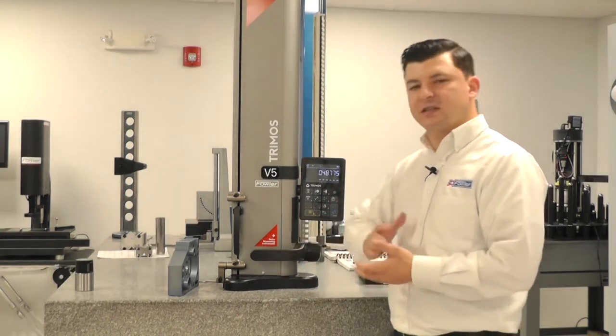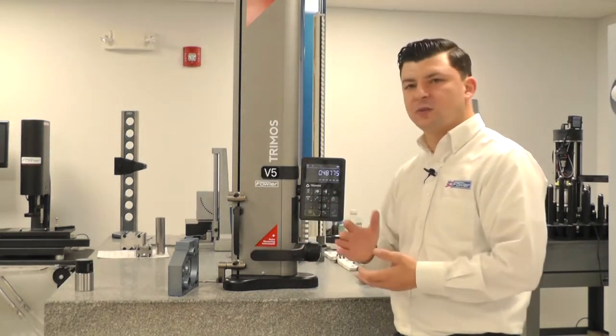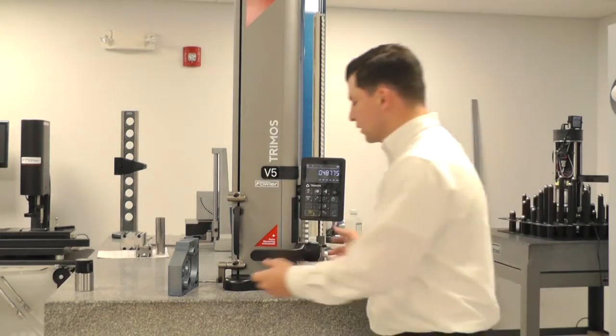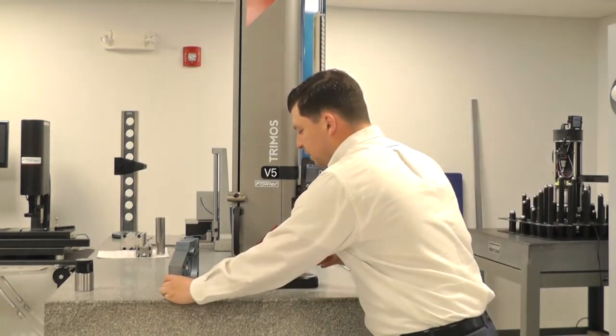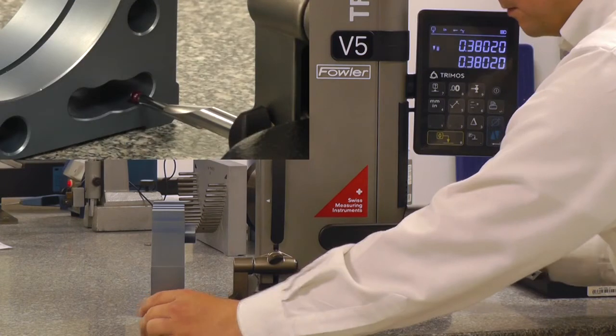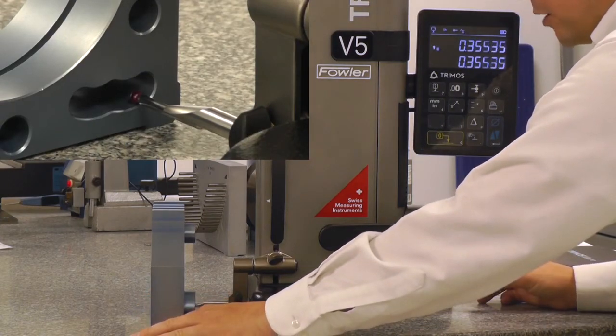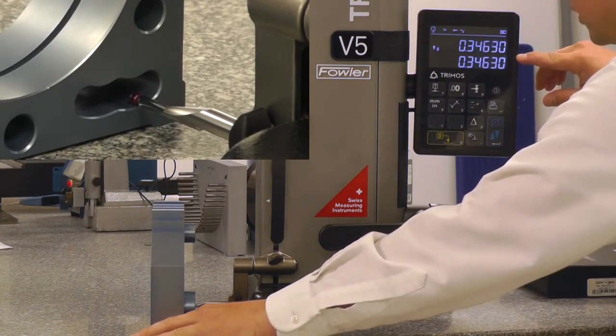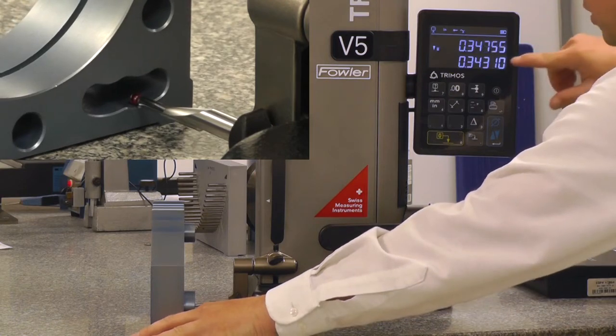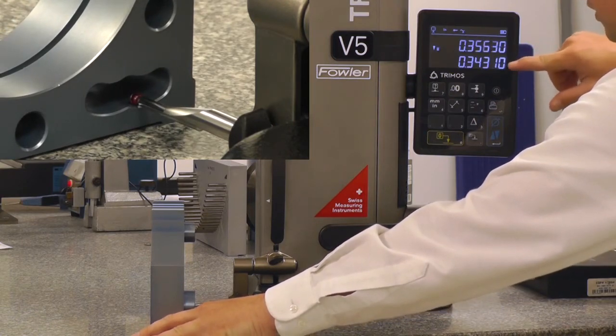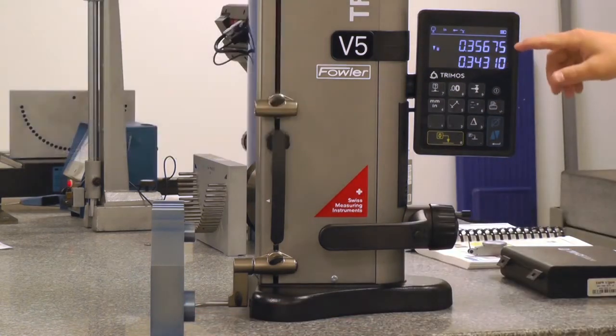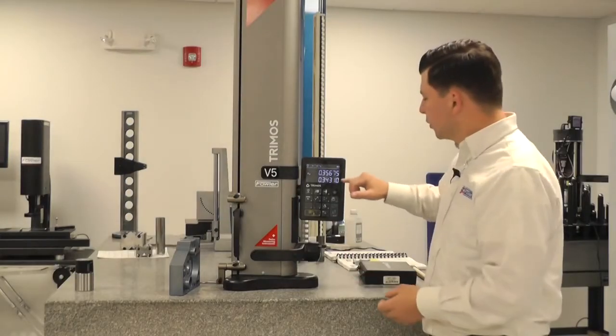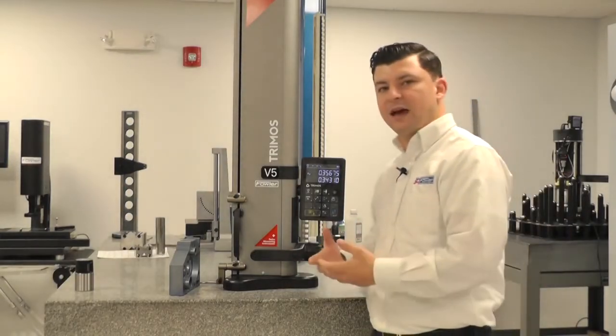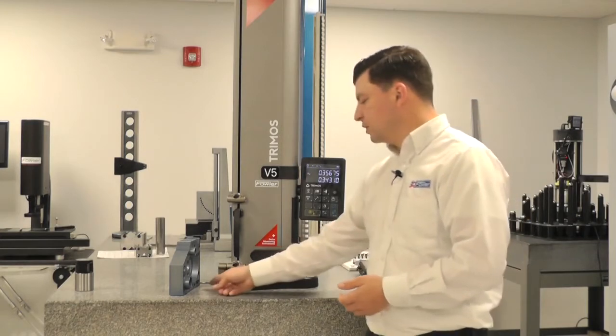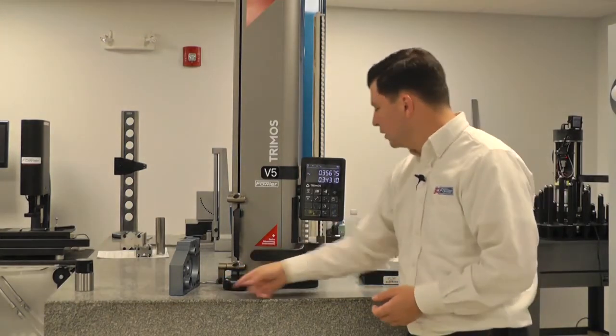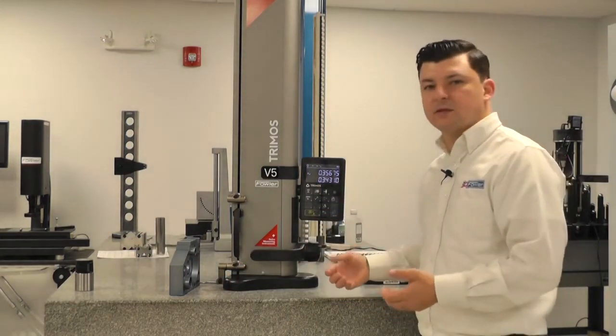It's like if you were using a test indicator and watching the needle sweep, it's going to do that for us automatically. So if I come in here and engage my probe, and as I sweep through the bottom, you're going to know that my numbers are getting lower and lower. Once I cross through that low point, my number freezes as my numbers on the higher side continue to grow. So we're locking on the lowest point in that valley. That's giving me a wall thickness relative to the plate of 343 thousandths.